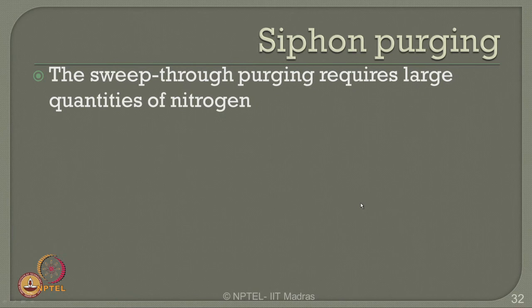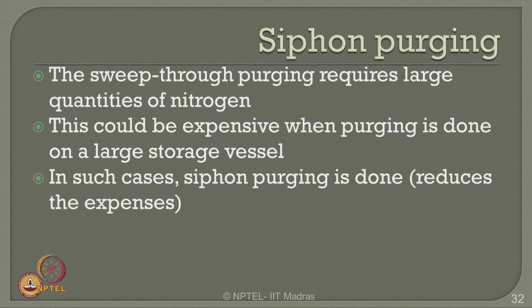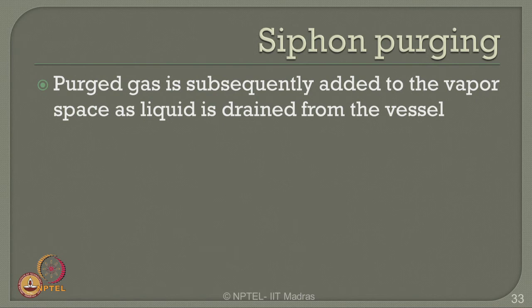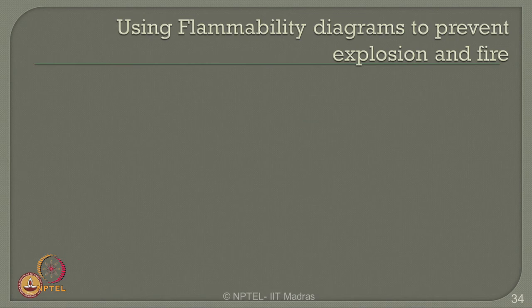One can also do siphon purging as a design method for reducing explosion damages. Sweep-through purging requires large quantities of nitrogen, which could be expensive for large storage vessels. In such cases, siphon purging is used to reduce expense. The purging process starts by filling the vessel with liquid, either water or any other compatible liquid. The purged gas is subsequently added to the vapor space as liquid is drained from the vessel. Volume of purged gas equals the volume of the vessel, and rate of purging equals the volumetric rate of liquid discharge.